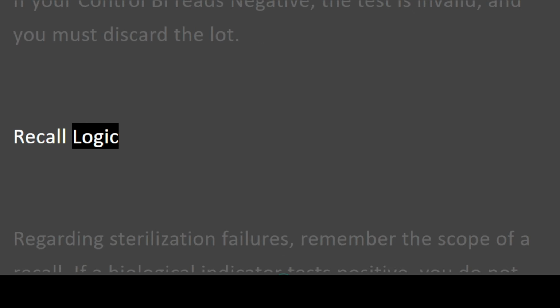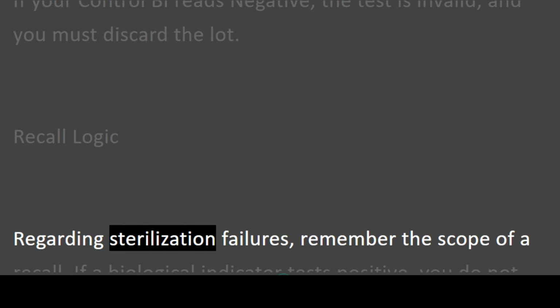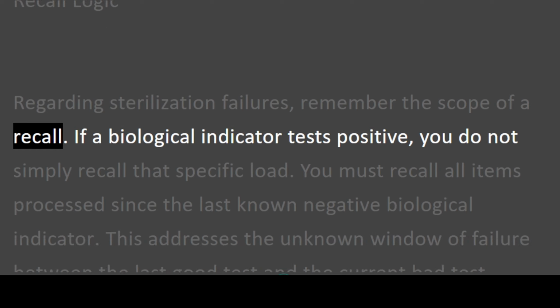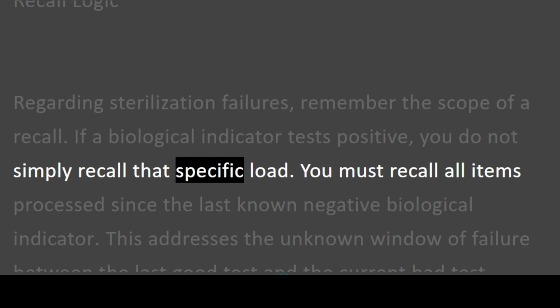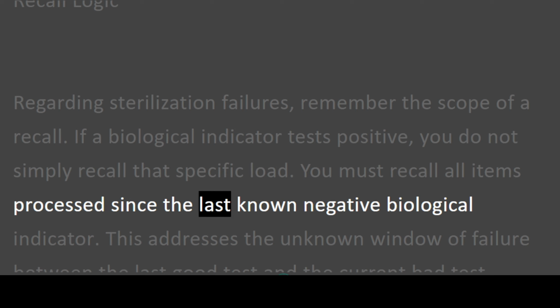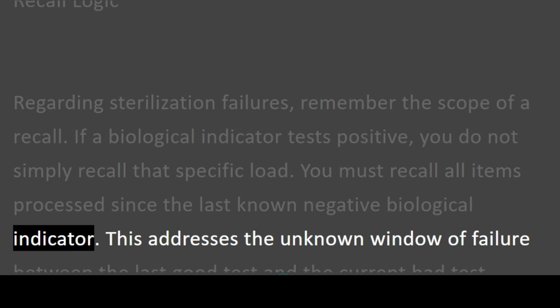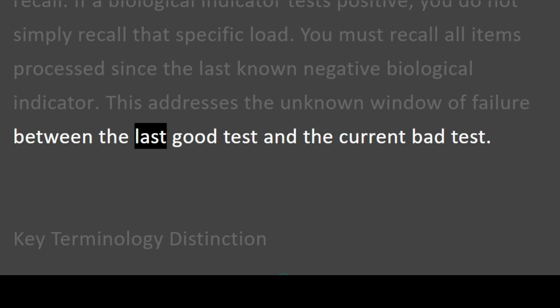Recall logic. Regarding sterilization failures, remember the scope of a recall. If a biological indicator tests positive, you do not simply recall that specific load. You must recall all items processed since the last known negative biological indicator. This addresses the unknown window of failure between the last good test and the current bad test.